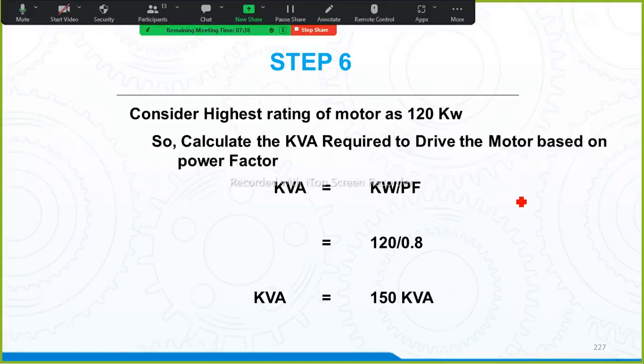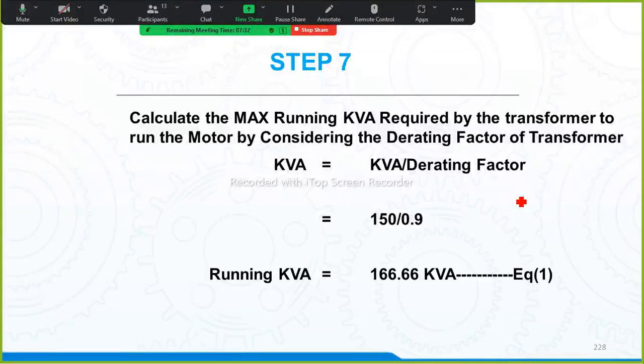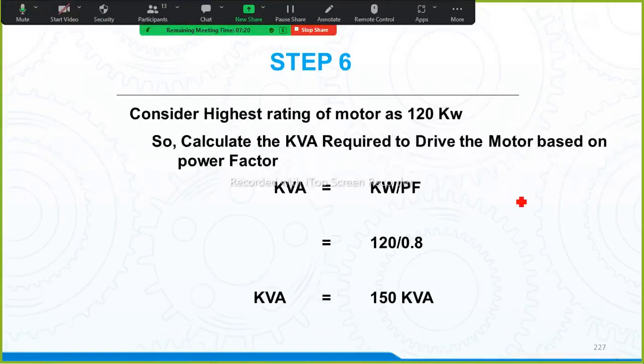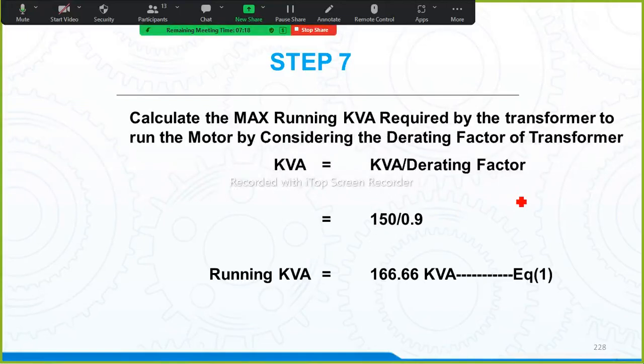Okay, now calculate the maximum kVA required to drive the motor based upon the derating factor of the transformer. So what I have done now is calculate the maximum running kVA required from the transformer to run the motor by considering the derating factor of the transformer. So kVA is equal to kVA divided by the derating factor: 150 divided by 0.9, we get 166.66 kVA.